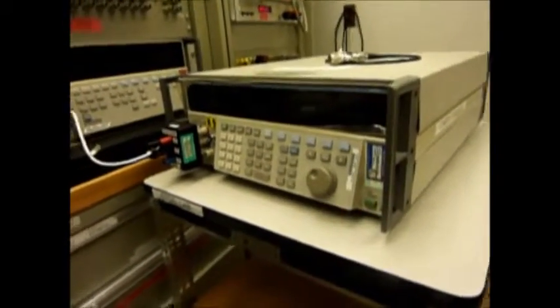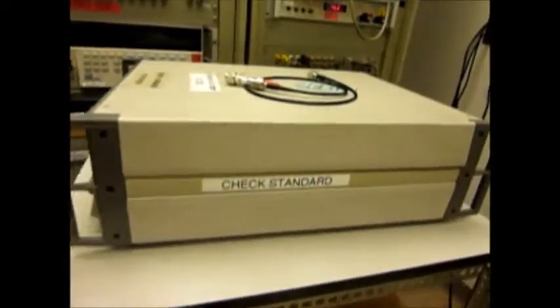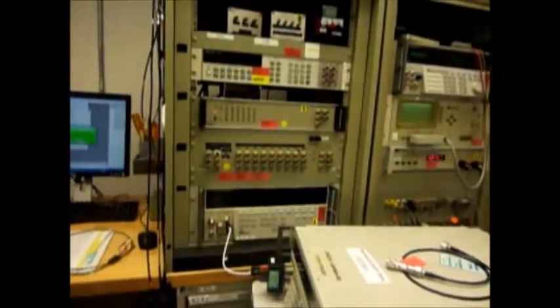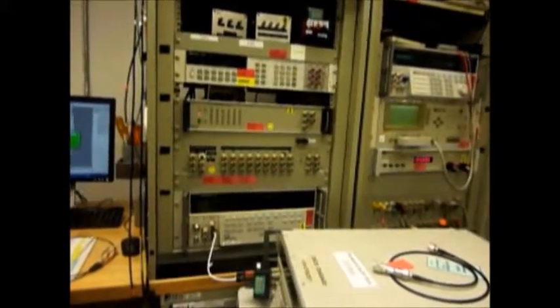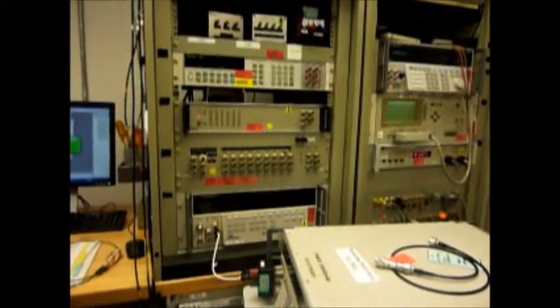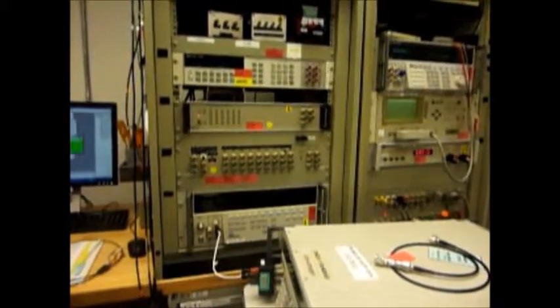Right now it's characterizing one of our check standard calibrators used in the manufacturing facility. All of the instrumentation in this panel is specifically characterized in individual test points and controlled through statistical process control under linear regression so that we know the accuracy and stability of any single test point at any given time.